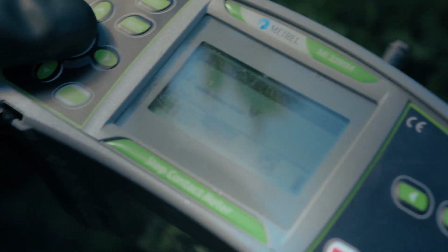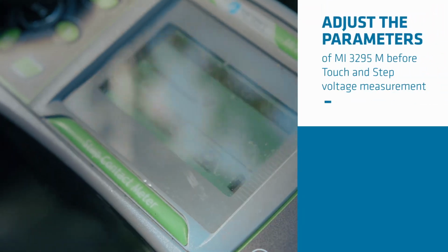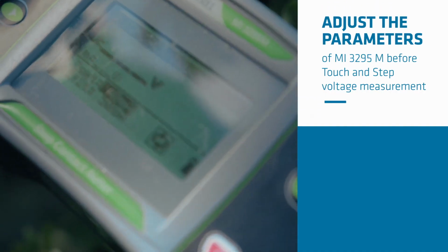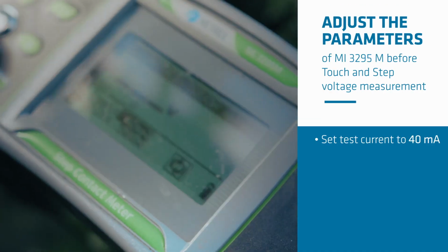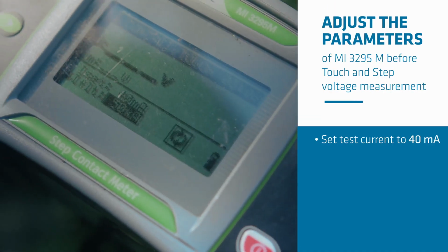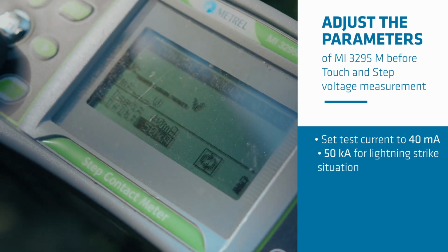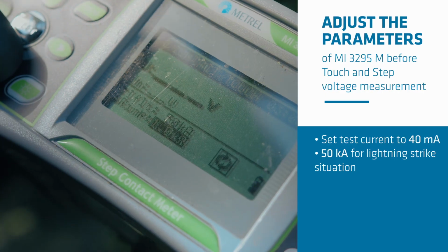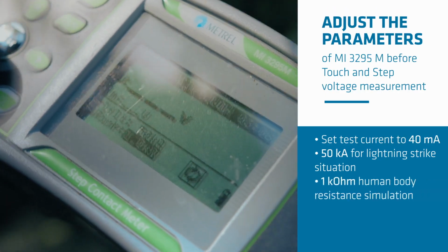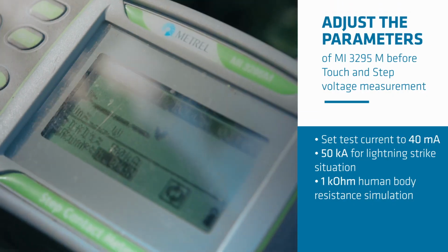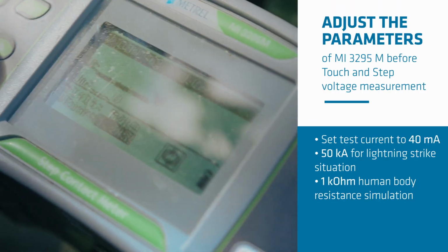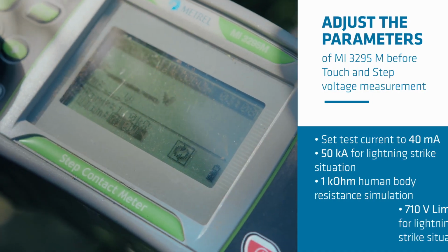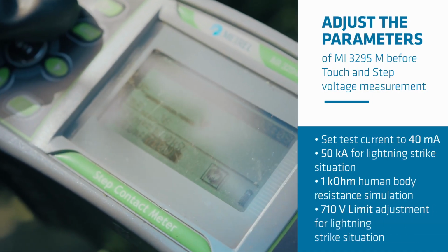For the purpose of testing, we need to prepare the instrument with some parameters to adjust. So we will put in the set current, the current which flows to the pylon now from all 4 legs, 40 milliamps. We will calculate the result to the volt as a lightning strike at 50 kiloamps. We will use the body resistance simulation. So the input resistance of the voltmeter is prepared for 1 kilo ohm, which simulates the resistance of a human body, and the limit parameter is set to 710 volts, which is the maximum allowed in a lightning strike situation. Okay, start with the measurement.